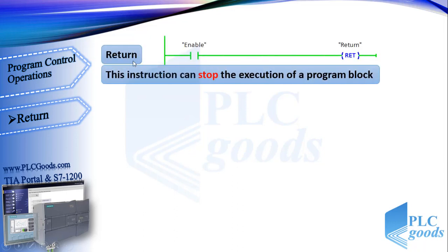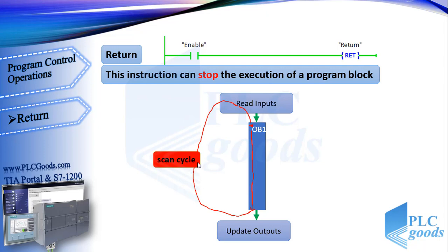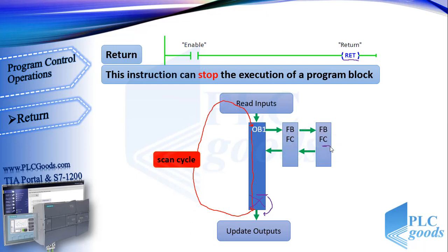The next instruction is return. This instruction can stop the execution of a program block. When a CPU is in running mode, it reads and stores the state of all inputs, then executes its program from the first network to the last in the main block OB1, then updates the state of all outputs. The CPU repeats this cycle, which we call the scan cycle. If a return instruction is used in the main block, the CPU won't execute the remaining networks — it exits from the main block and repeats its scan cycle. If we use the return instruction in a function block or function, the CPU will return to its previous block.